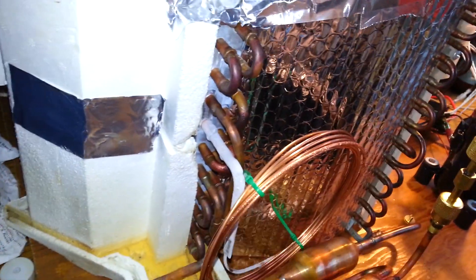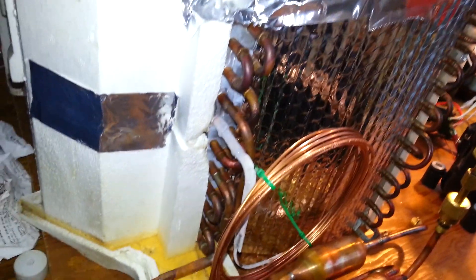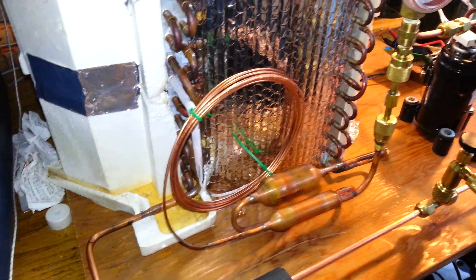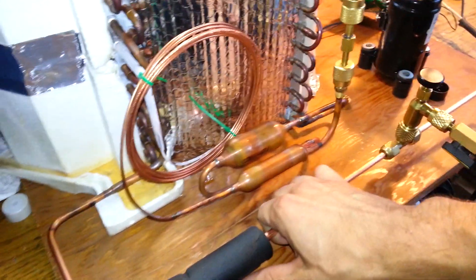It only frosted about for one, not even one whole loop. A little bit of condensation, just not nearly enough refrigerant flow. A hell of a lot of superheat coming back.